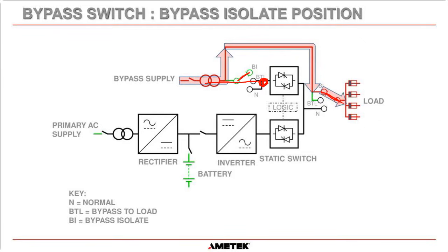between inverter and bypass. But what this allows us to do is, if we open this AC input breaker and open that battery breaker, because of the bypass isolate position, it removes power from here and from here. Everything inside the UPS is now volt free, and we can replace parts safely using NFPA 70 practices. Okay.